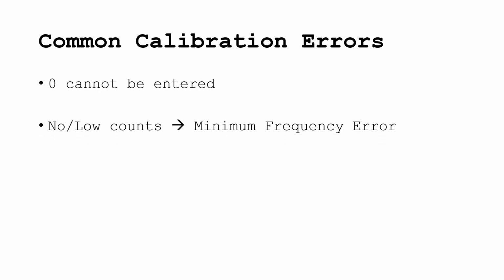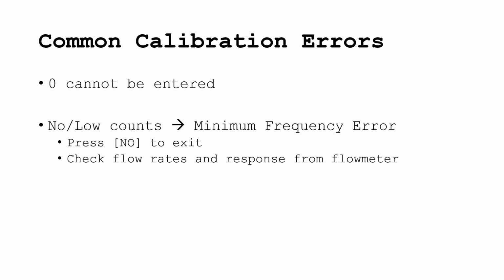Some common calibration errors are: 0 cannot be entered for a calibration. If no counts or low counts, less than 1 per second, are detected, the system will alarm with a minimum frequency error. If this occurs, press the No key to exit and check the flow rate as well as the response from the flow meter. Make sure the gears are not jammed and the meter is counting up during the calibration.